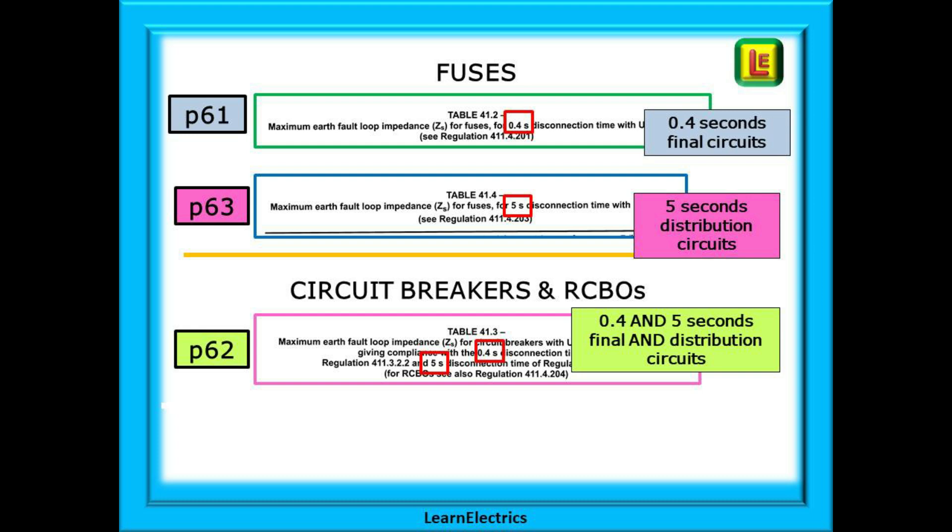One for final circuits and one for distribution circuits. The table on page 62 is different. It is for circuit breakers and RCBOs and covers both 0.4 seconds and five second times. So on page 62 we use table 41.3 for both final circuits and distribution circuits.